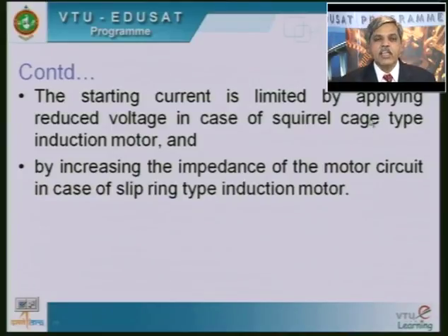Therefore, the starting control has to be done from the supply side, that is the stator side. Whereas in the case of the other type of rotor, that is the wound rotor or slip ring type induction motor, it is possible to add an external resistance to the rotor circuit through the slip rings. So, addition of resistance increases the rotor impedance, thereby the starting torque of the induction motor increases.